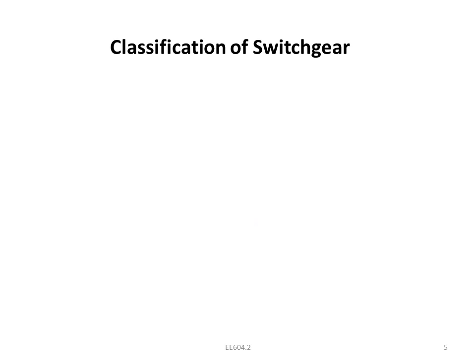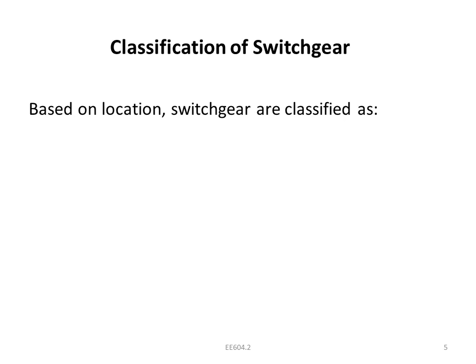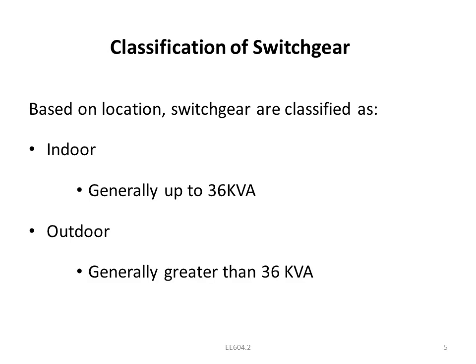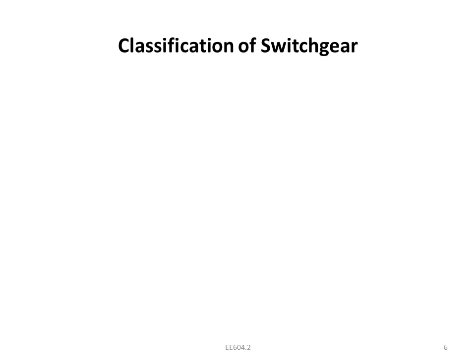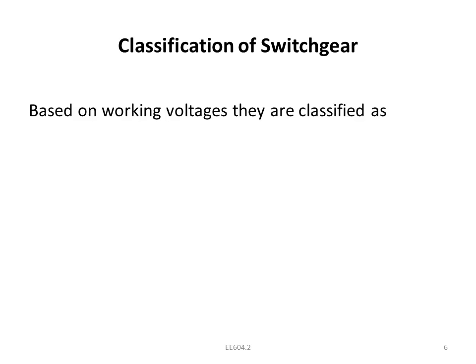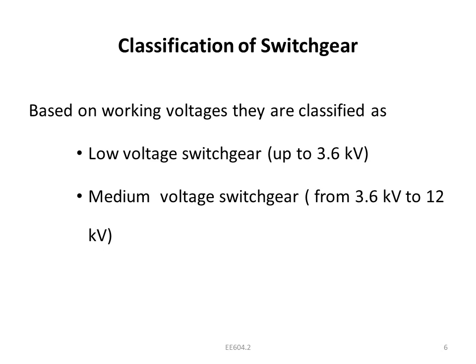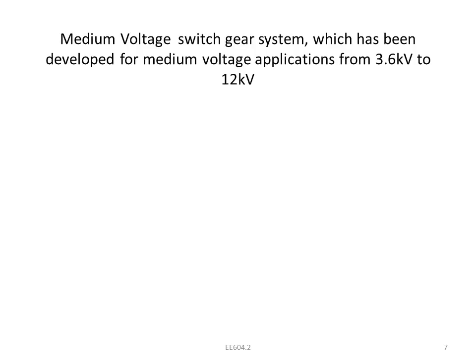Classification of the switchgear. First, the classification based upon the location: switchgears are classified as indoor, generally up to 36 kV, and outdoor, greater than 36 kV. Classification based upon the working voltage: low voltage switchgear, that is up to 3.6 kV, medium voltage switchgear, that is 3.6 to 12 kV, and high voltage switchgear, that is beyond 12 kV. Low voltage is what we have in our homes, domestic. Medium voltage switchgear is developed for 3.6 to 12 kV.